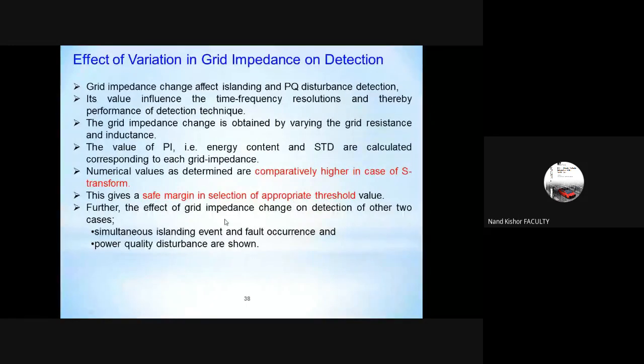Further, the effect of grid impedance change on detection for two other cases we have analyzed: the case of simultaneous islanding event and fault occurrence, and then power quality disturbance. So this is a study we performed. On this slide, in fact, how do the energy content and standard deviation vary for the case of islanding for different grid impedance?